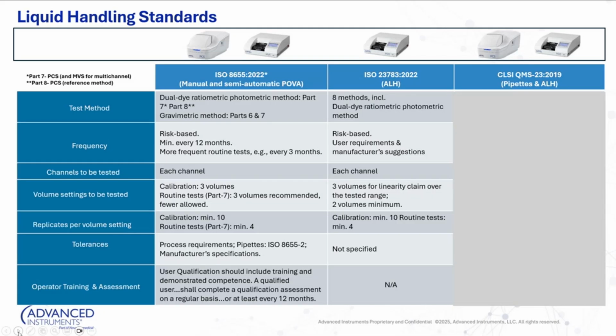So lots of autonomy with 23783. That's intentional. It's really the first version, if you will, with regards to automated liquid handlers. I think we'll probably see as the years go by that ISO might put a little bit more detail around the recommendations and requirements in that standard. The channels to be tested, much like 8655, every channel. Volume settings, much like 8655. So if you're looking to claim linearity, testing 3 volumes over the testing range of that automated liquid handler and its head that you're testing with it will give you the ability to calculate linearity across the device.